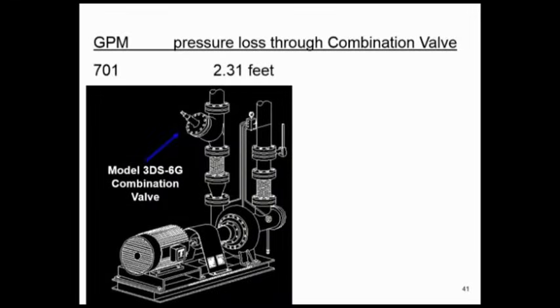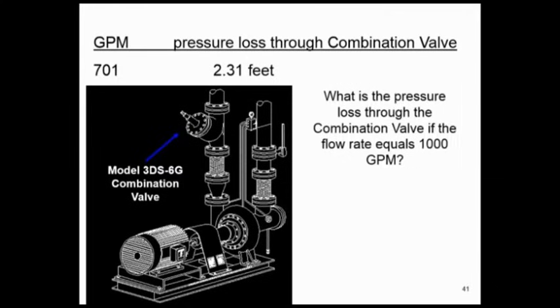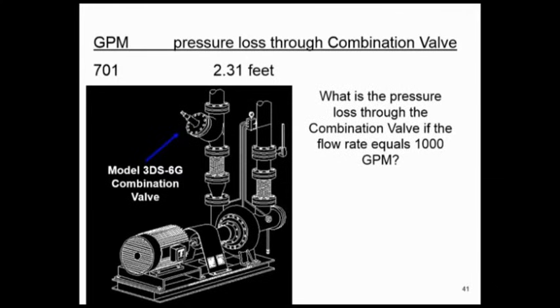So here we go with a pump. I got a base mounted end suction pump here. I got a flow rate through this pump of 701 GPM. I have installed on this pump a calibrated balancing valve, which for us is a triple duty valve. And there's your pipe size, and there's your model of the valve. Now, the question would be, if I know the pressure drop through this device when it's wide open, and I'm not going to change the position of it, is 2.31 feet at 700 GPM, how can I come up with a pressure drop at 1,000 GPM?